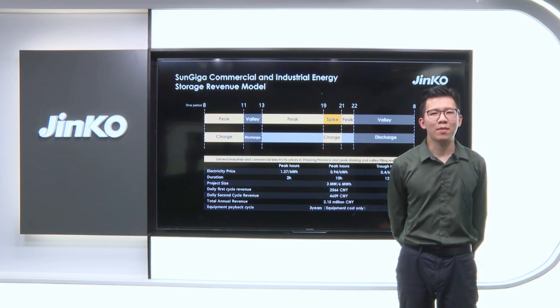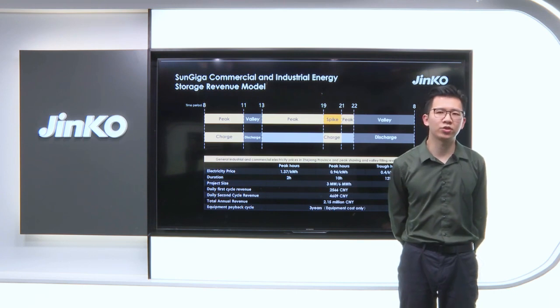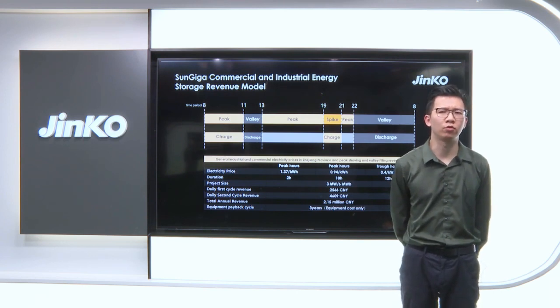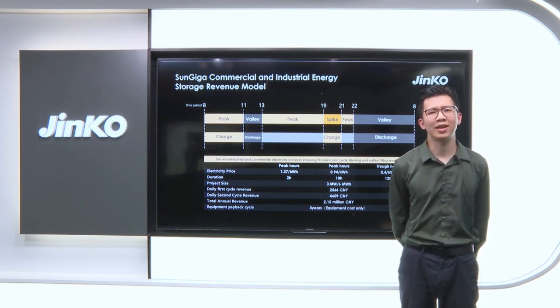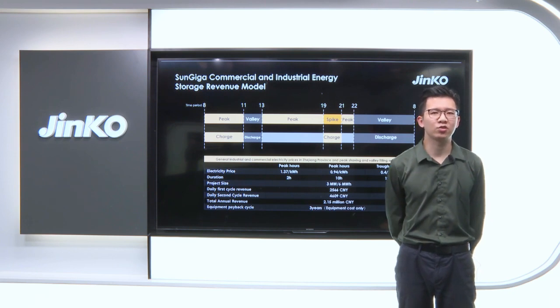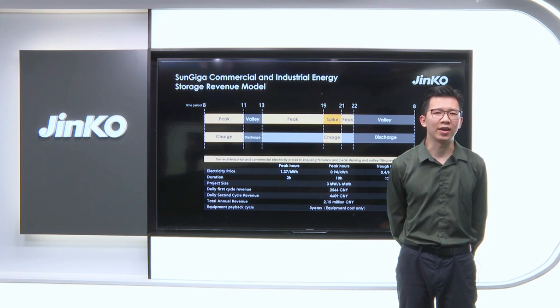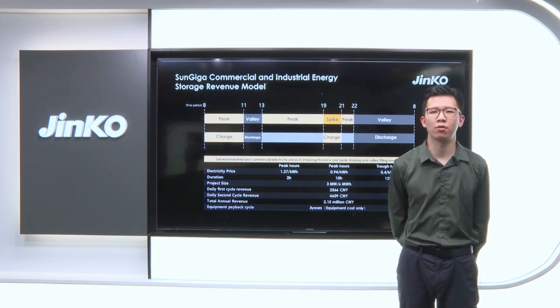We can do the same math, assuming the project size is 3 megawatt and 6 megawatt hour. The first charging and discharging revenue is 2,500 yuan per day. The second charge and discharge revenue is 4,600 yuan per day. The total annual revenue is 2.1 million yuan per year. If we only calculate the cost of the equipment, the equipment payback cycle is only 3 years.